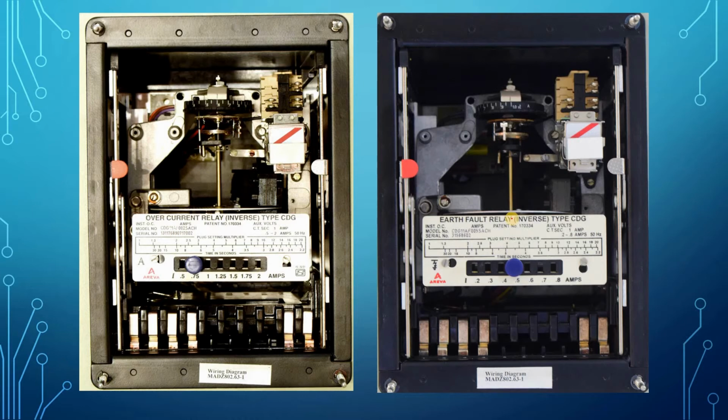That means any leakage current flowing from the transformer body to ground, or any equipment to ground, or any equipment neutral to ground, should be detected. That means this should be more sensitive. I am repeating, the earth fault relay should be more sensitive compared to the overcurrent relay. That's why it starts from 0.2. It can detect 0.2 ampere of current as a fault current, but this one can detect 0.5. Below 0.5 it will treat it as normal operating current.